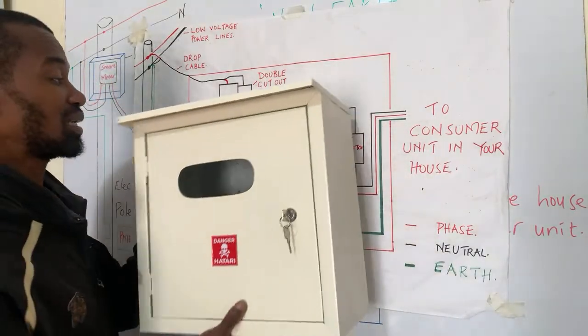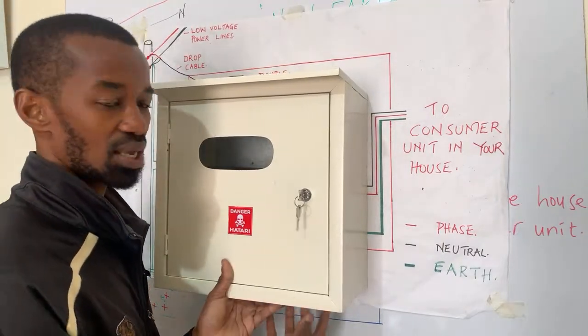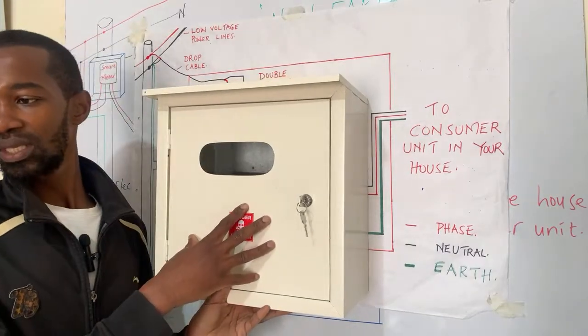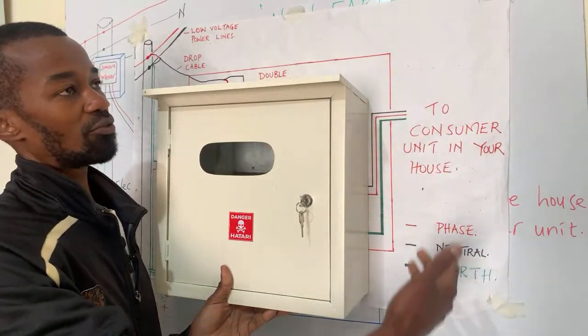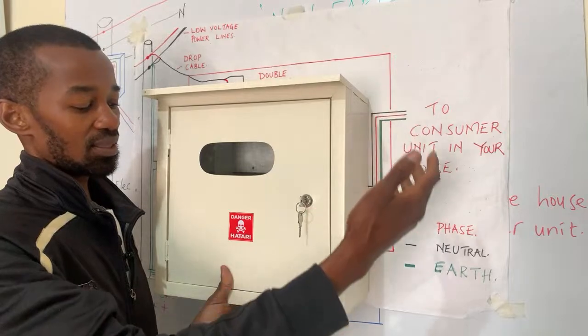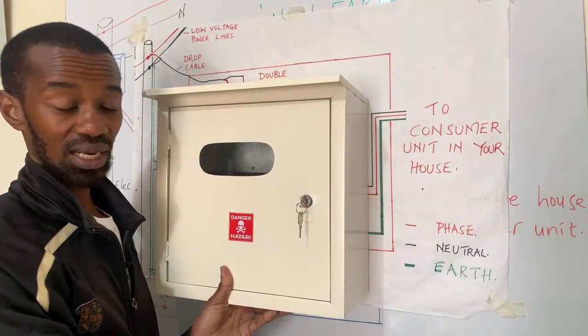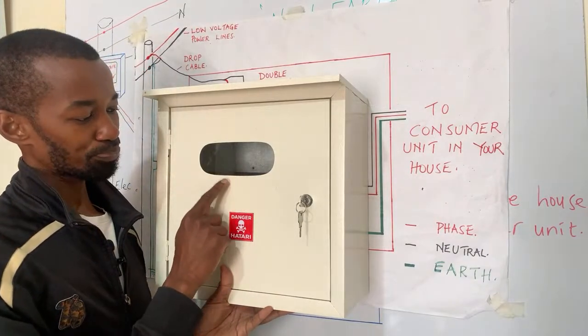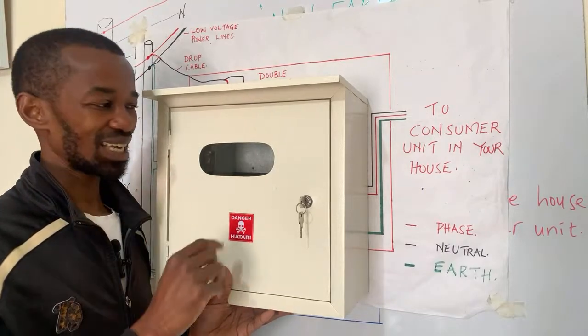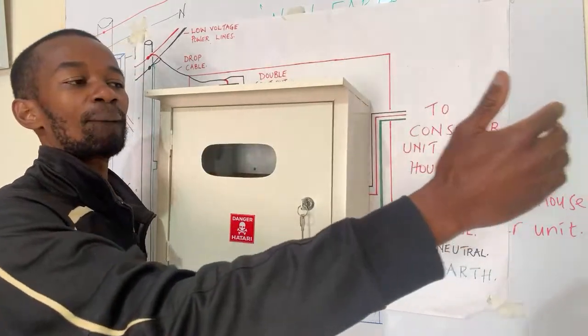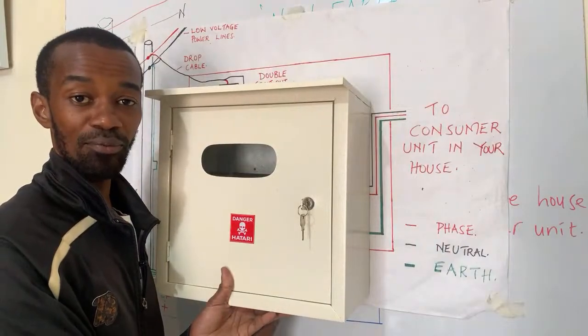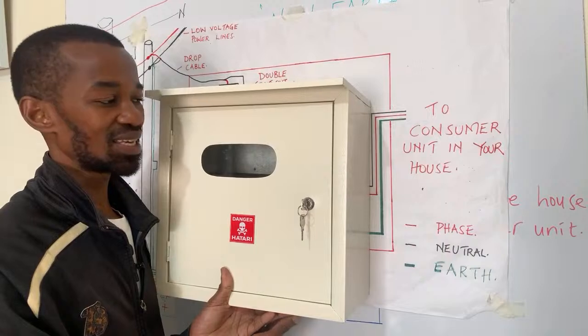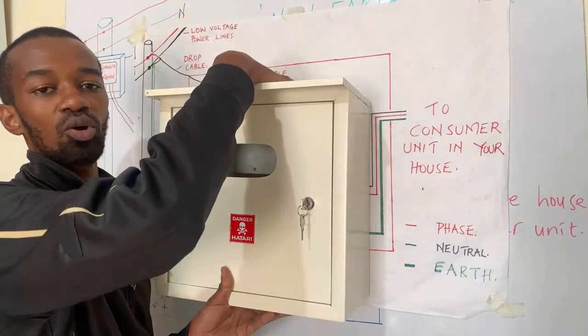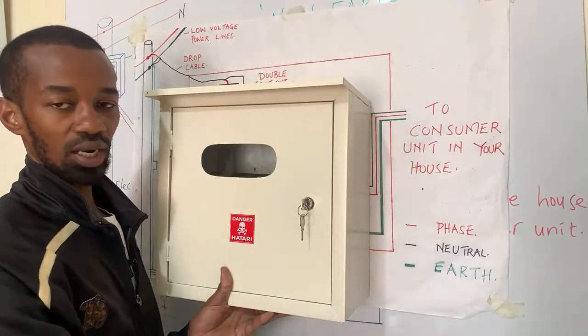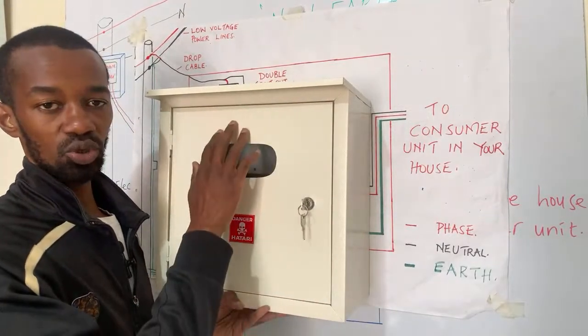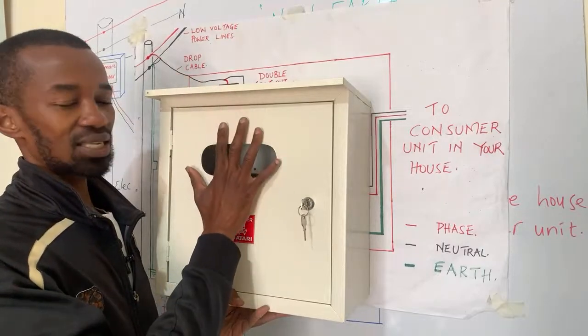The reason I have my meter box connected so that all cables exit at the bottom is so that if water flows down the drop cable from the national grid, it finds its way to the ground and does not enter the meter box. Also, the cables that exit the meter box to the installation or house come from the bottom, so that any rainfall landing on top of the meter box falls to the ground and doesn't interfere with the connection inside. A metallic meter box has to be earthed, that is very important.